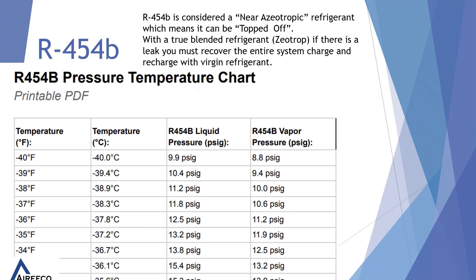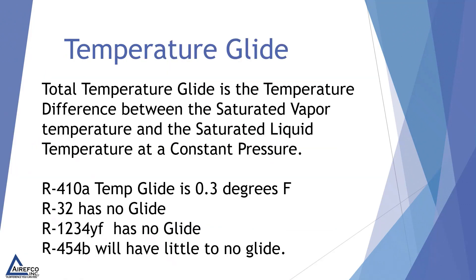Some preliminary charts released for R454B show a liquid pressure and a vapor pressure column, but R454B is considered a near-azeotropic refrigerant, meaning it can be topped off like R410A. With a true blended zeotrope refrigerant, if there is a leak you must recover the entire charge and recharge with virgin refrigerant. Total temperature glide is defined as the temperature difference between the saturated vapor temperature and the saturated liquid temperature at a constant pressure.